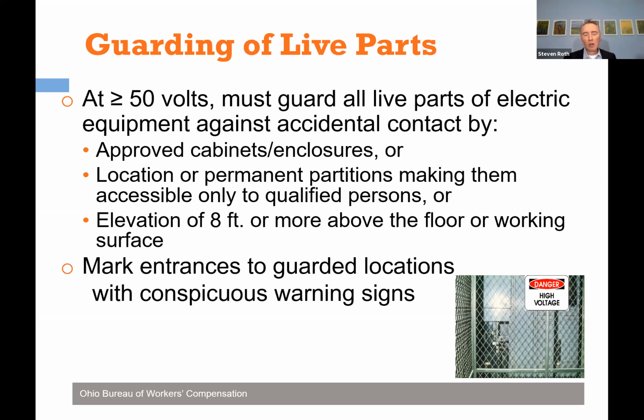Properly trained, but also with the proper PPE on to enter it. OSHA has this gray area that says if it's more than 8 feet off the floor, I don't need to guard it or cover it. Well, 8 feet off the floor is great, but I can almost touch 8 feet myself, and if I stand on my tiptoes, I can definitely touch it with my fingertips. So 8 feet isn't high enough. And as soon as I stand on anything to gain elevation, whether it's a ladder, step stool, or scissor lift, I'm closer to it. So that 8 feet no longer works.